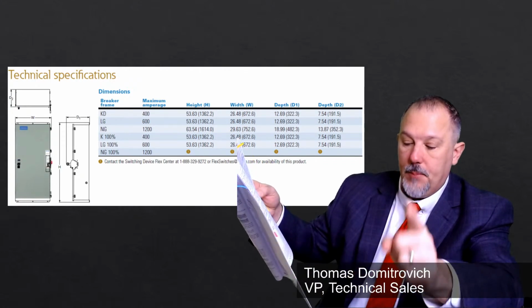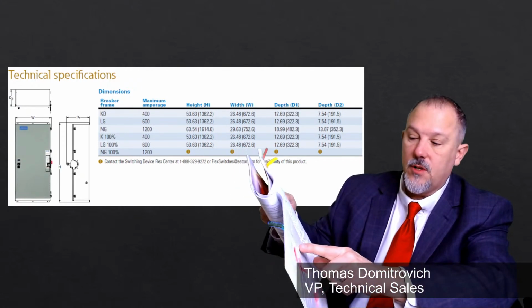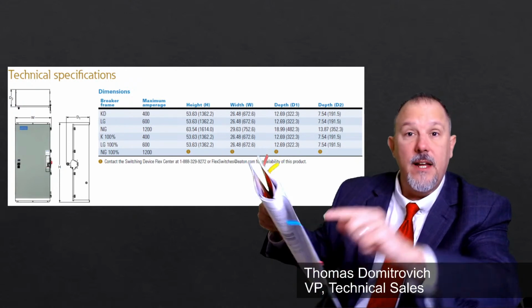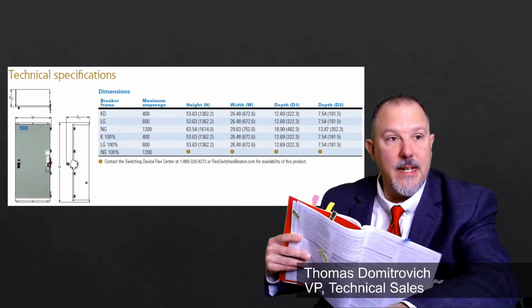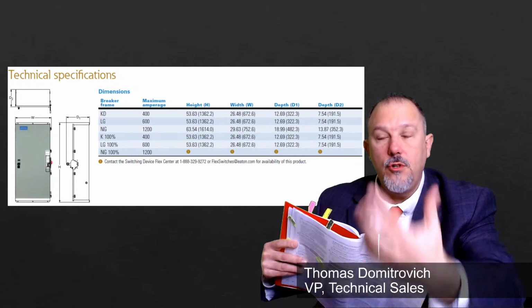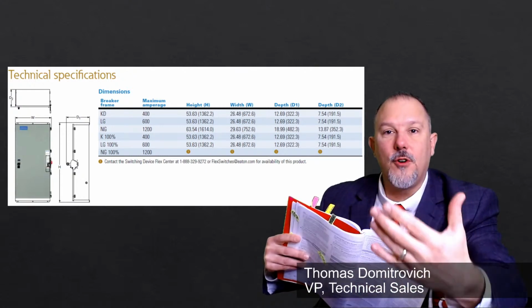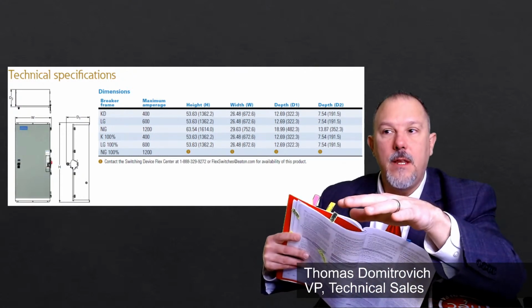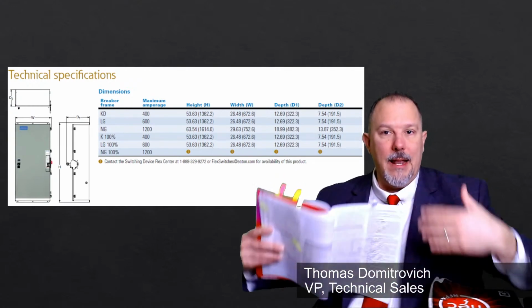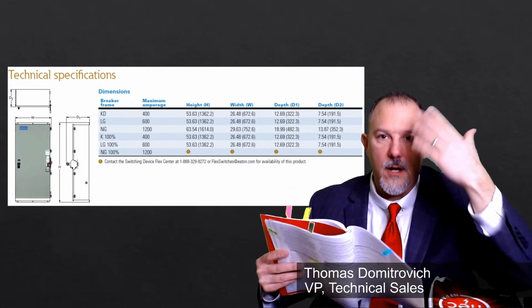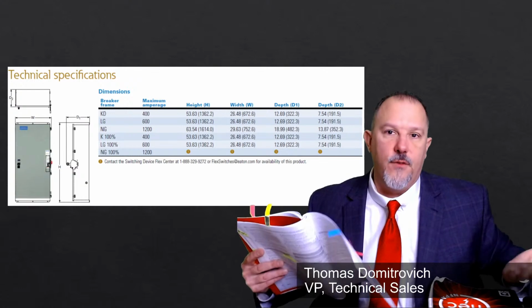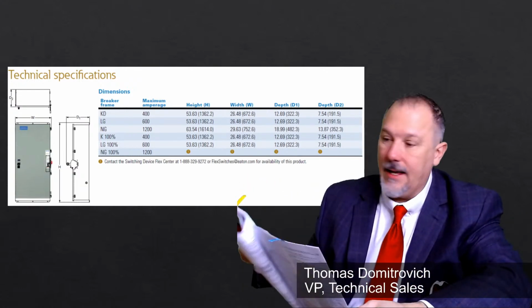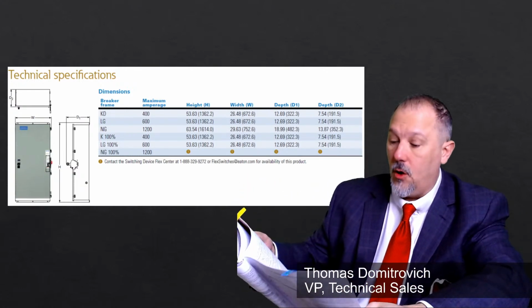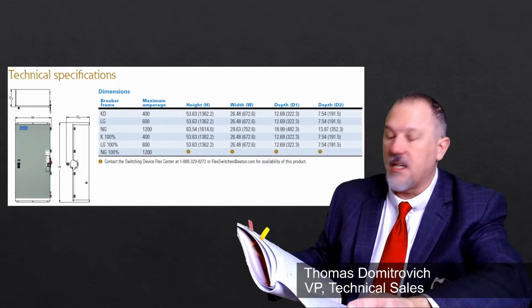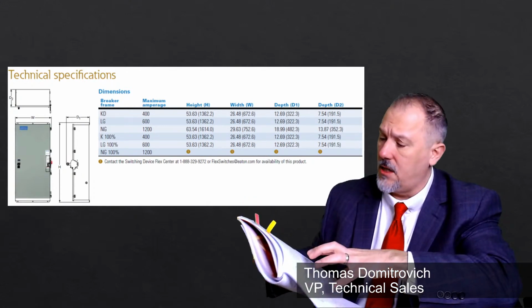130.2(B), elements of a work permit, requires the results of the arc flash risk assessment. Think about it: if this piece of equipment is ahead of you, your arc flash risk assessment will show the severity is very low—light wear, maybe just gloves and goggles. You won't need a 40 cal or 8 cal suit, just daily wear with some light PPE, but follow the procedures here.